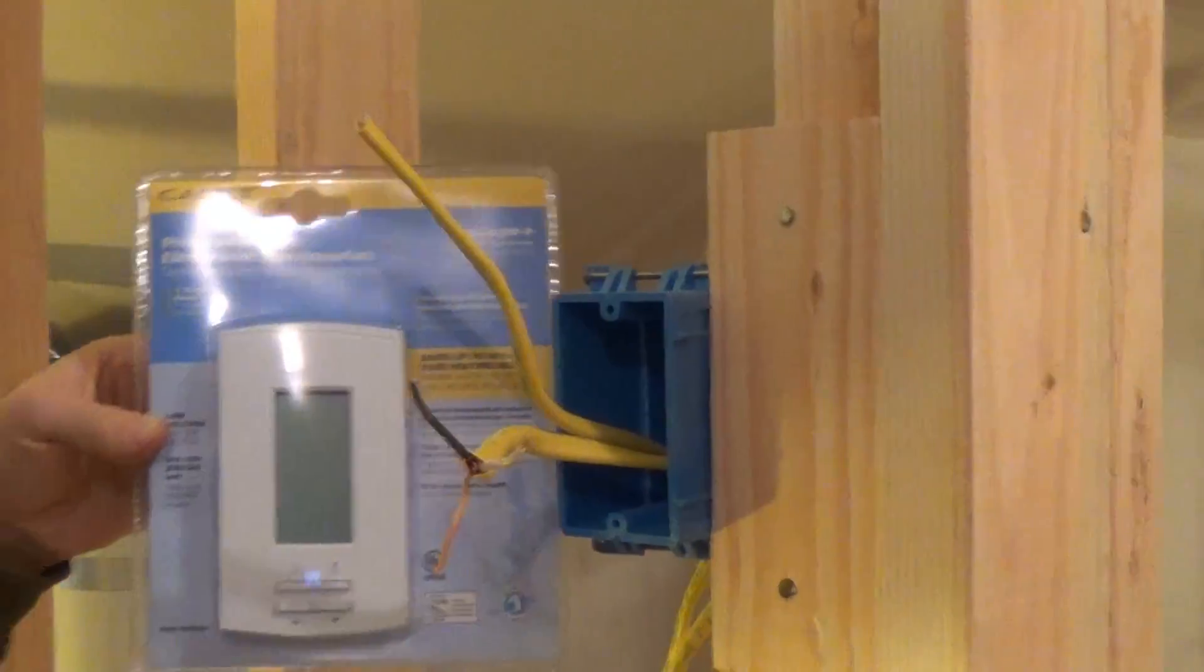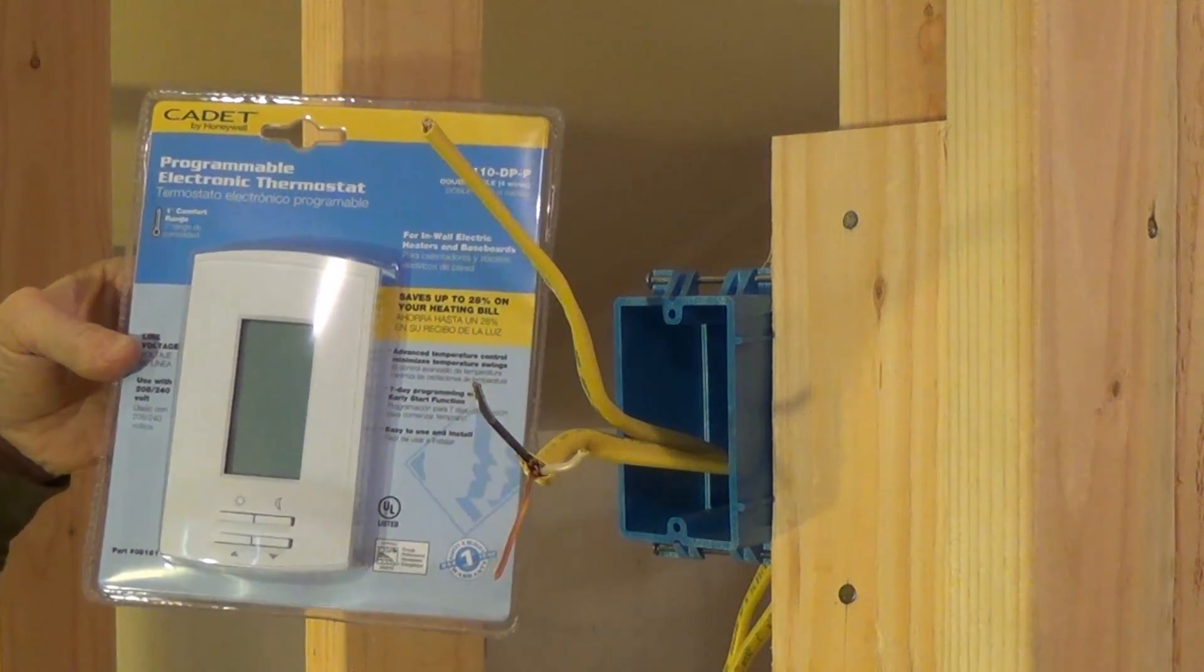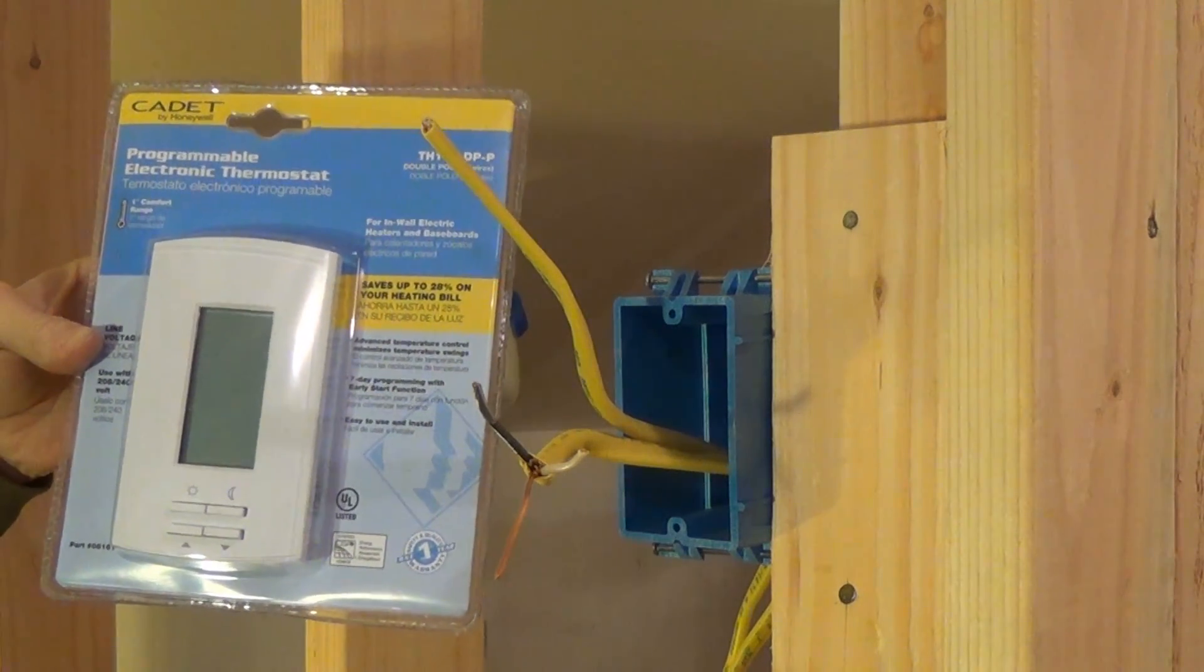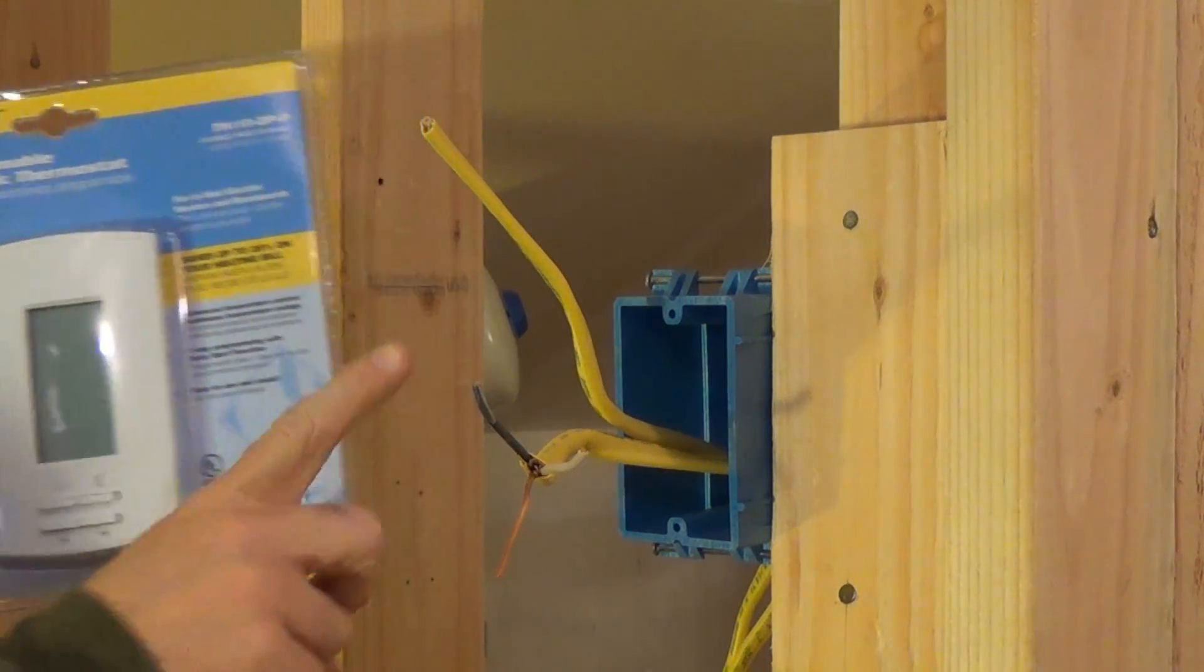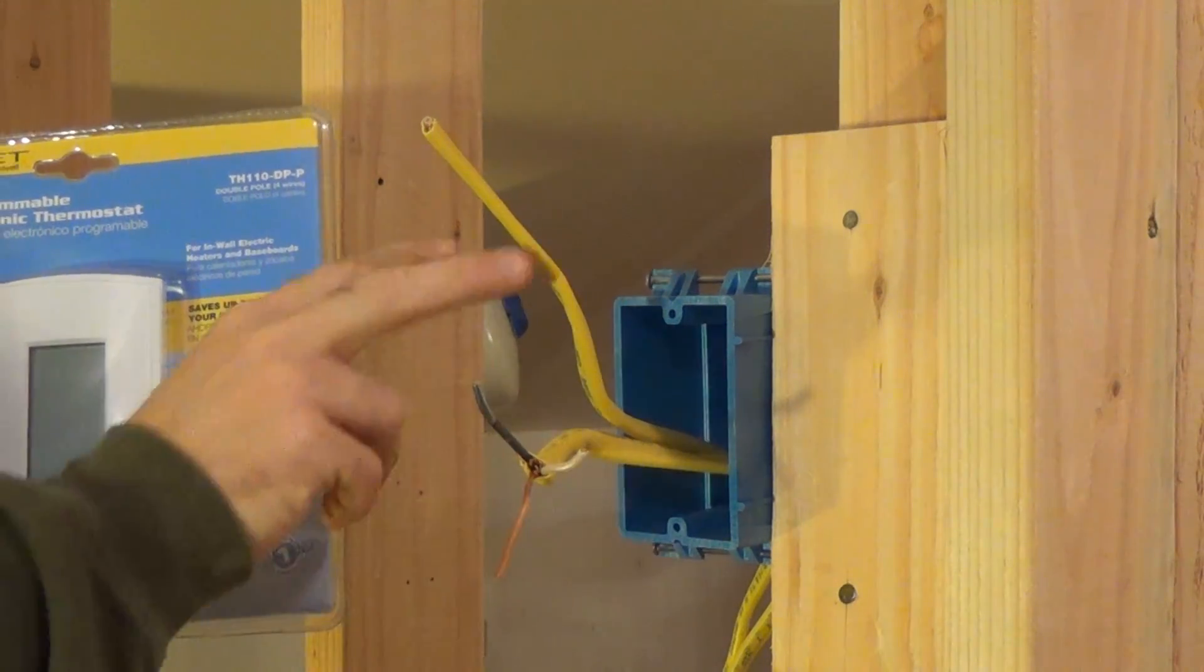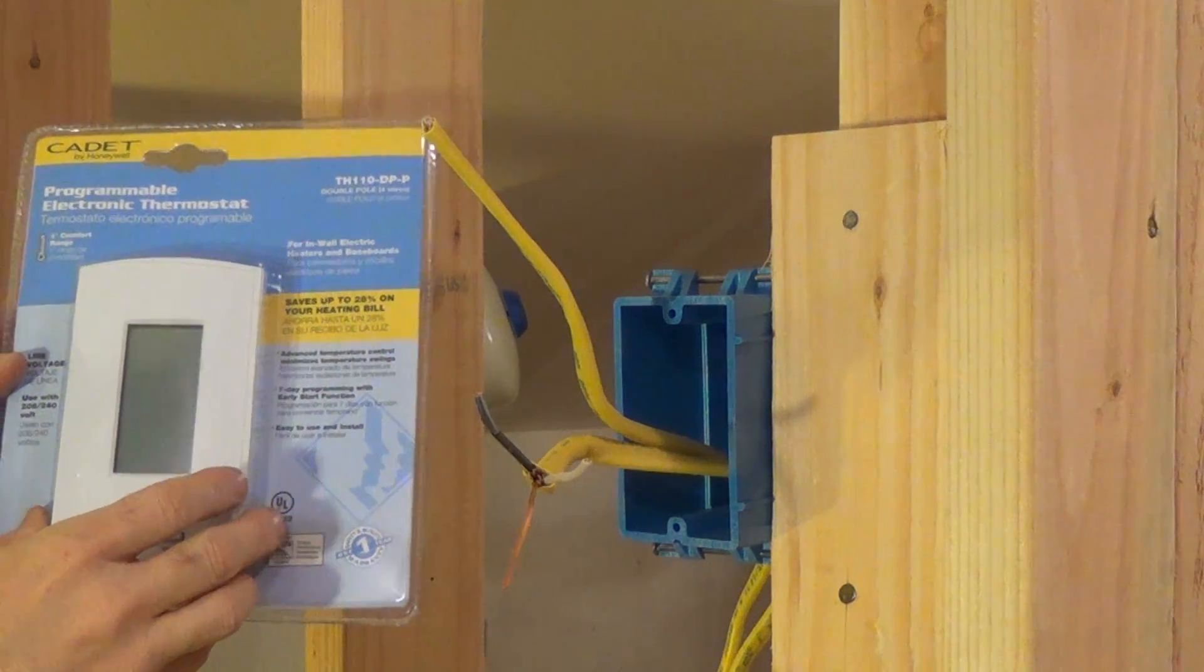let's see if I can focus here, yeah you got it there. This is a programmable electric thermostat for cadet heaters and this is a double pole system. I have a 240 volt line coming in and then this one's going up and I'll show you how to wire it up today.